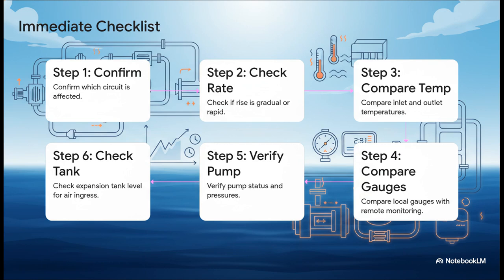1. Pinpoint the exact circuit. Is it the high temp or low temp system? 2. Is the rise happening slowly over an hour, or did it just jump up? 3. Check your delta T. Compare the inlet and outlet temperatures across the cooler. Is it actually doing its job? 4. Get up from your chair. Go compare the screen in the control room with the actual mechanical gauge on the pipe. Verify your data. 5. Check your pump pressures. And 6. Check the expansion tank level. You do all this before you touch a single thing. You gather the facts first.